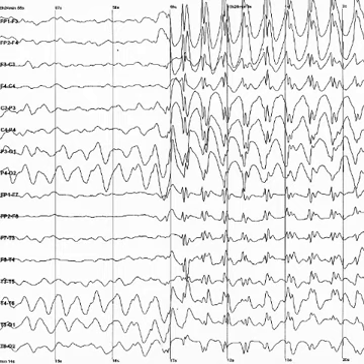Analog-to-digital sampling typically occurs at 256 to 512 Hz in clinical scalp EEG. Sampling rates of up to 20 kHz are used in some research applications. During the recording, a series of activation procedures may be used. These procedures may induce normal or abnormal EEG activity that might not otherwise be seen. These procedures include hyperventilation, photic stimulation, eye closure, mental activity, sleep and sleep deprivation. During epilepsy monitoring, a patient's typical seizure medications may be withdrawn.